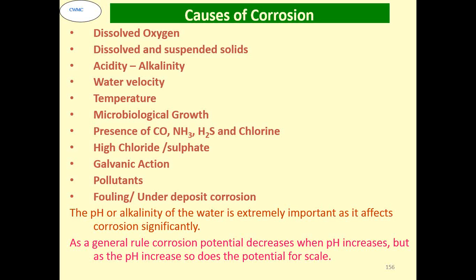What are the causes of corrosion? Dissolved oxygen, dissolved and suspended solids, acidity or alkalinity, water velocity, temperature, microbiological growth, presence of CO, carbon monoxide, ammonia, H2S, carbon dioxide, chlorine, high chloride or sulfate, galvanic action, pollutants, and under-deposit corrosion. The pH alkalinity is extremely important as it affects corrosion significantly. As a general rule, corrosion potential decreases when pH increases. But as the pH increases, so does the potential for scale.